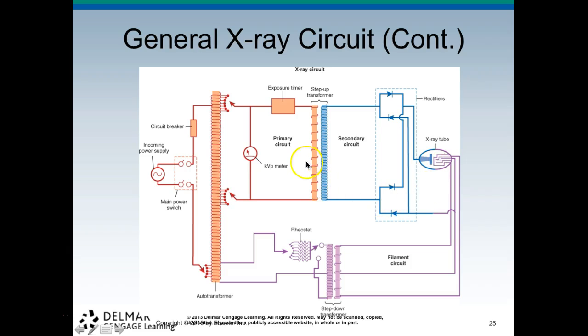All right, so we have the step-up transformer and we have rectification to make sure that we have direct current. You've got to have direct current going to your X-ray tube. And here on your filament side of the circuit, we have some rheostats, and you can see it's a step-down transformer. There are two lines coming off, and the two lines are for your small filament and your large filament.